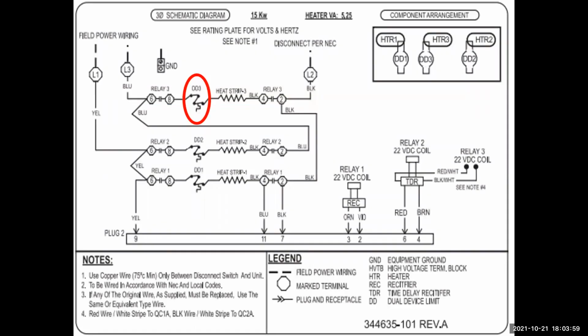Okay, again, we're going to do a quick review of the wire diagram. If you notice the new dual limit switch, it's marked here with a DD. The new limit switch has a redundant switch to open the circuit for extra safety on the new B series style heaters. This will be on the 15 kW and under. So here's a good little look at it. We've got a temperature switch, limit switch here. Usually you have one open switch. If this would get stuck closed, we have another one that can open. So we've got redundancy on our switch.